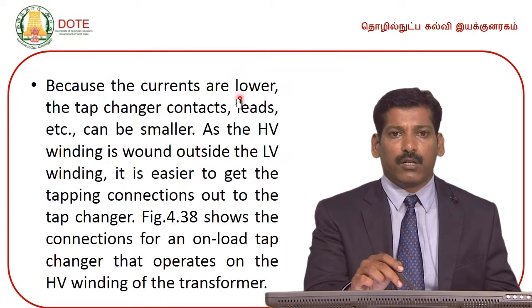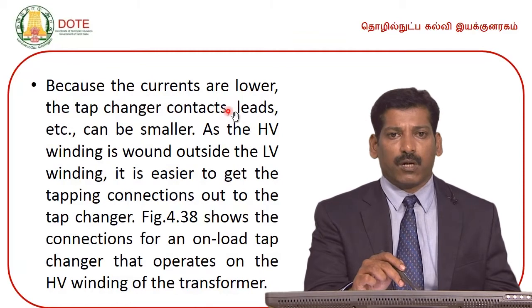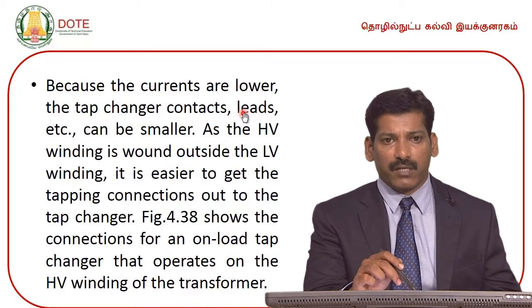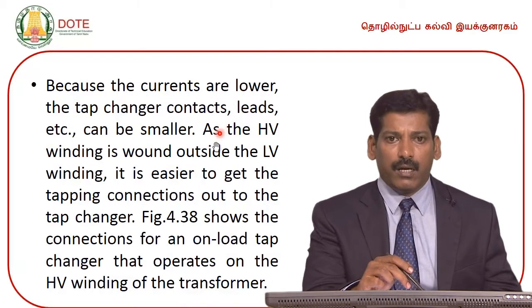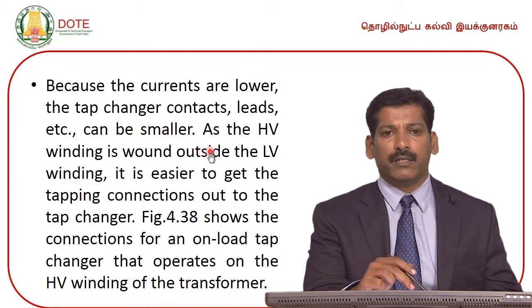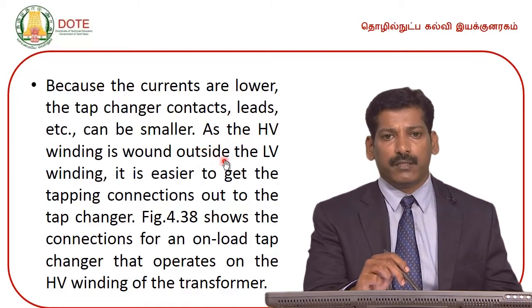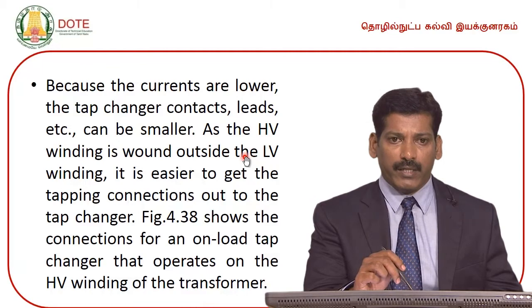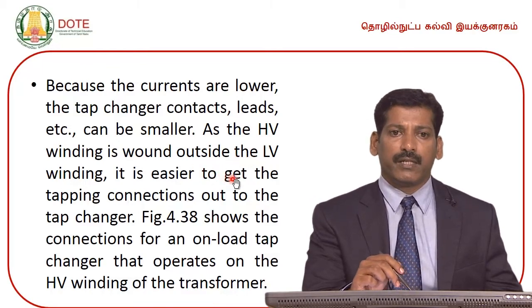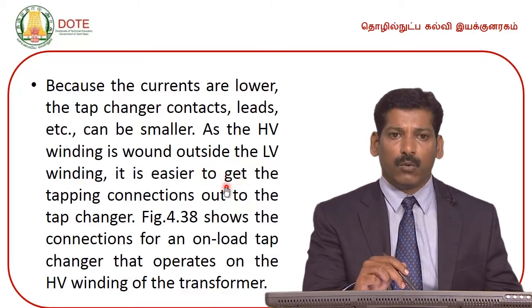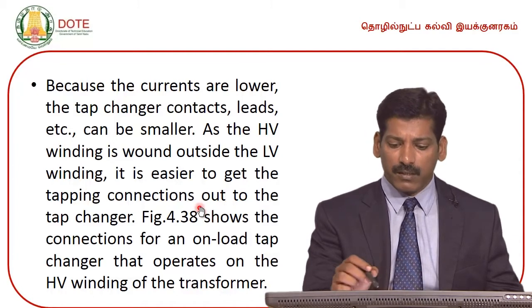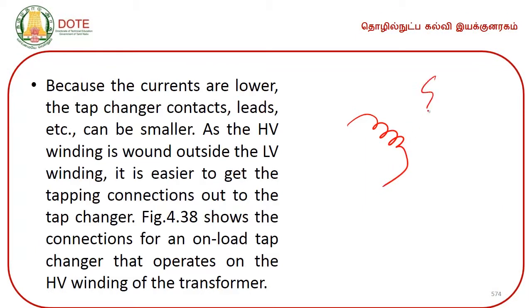Because the currents are lower, the tap changer contacts, leads etc. can be smaller. As the high voltage winding is wound outside the low voltage winding, it is easier to get the tapping connections out to the tap changer. This is because we have already seen this in the construction of transformers. So, this is the primary and this is the secondary.